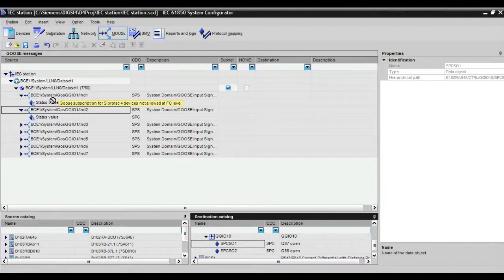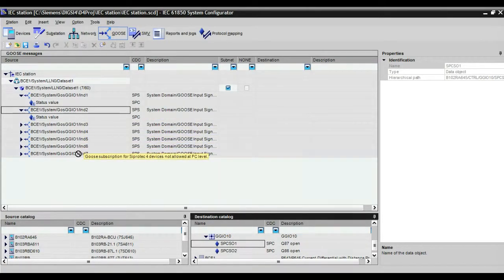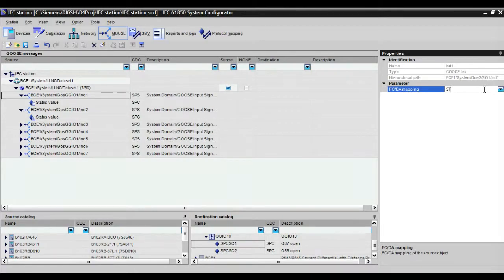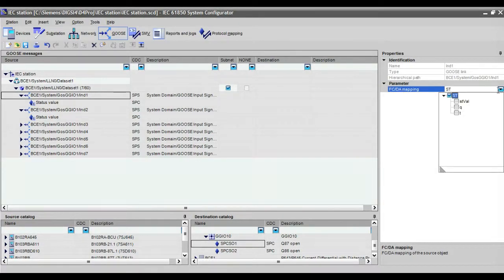But when you go for GOOSE between a Siemens and Micom relay you will get this message: FC level. This is due to the status value of the signal which you got in virtual output — it is having ST value and Q value, all values. So we have to change it into ST value only. You click on the status value, and on the right-hand side you can see FC/DA mapping. There will be a selection option for ST — click on that and select ST value. Do the same for all remaining signals.